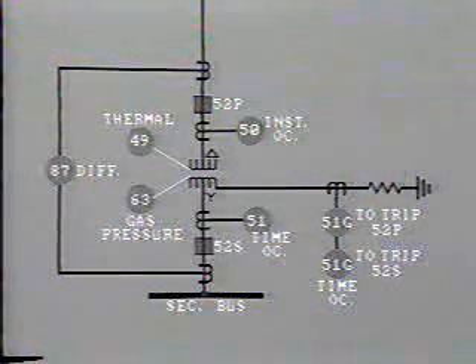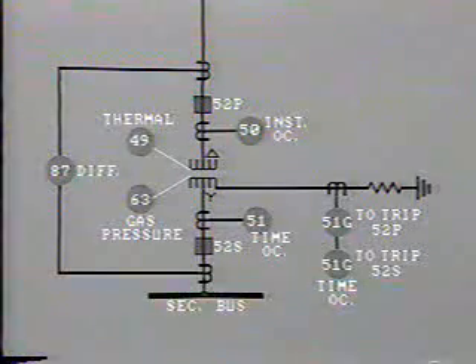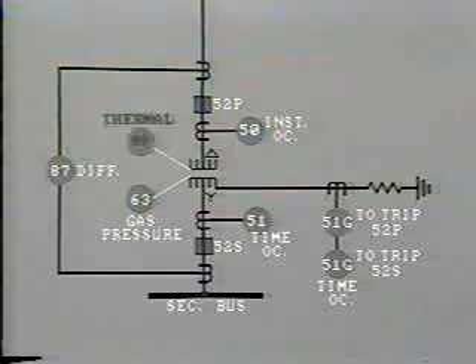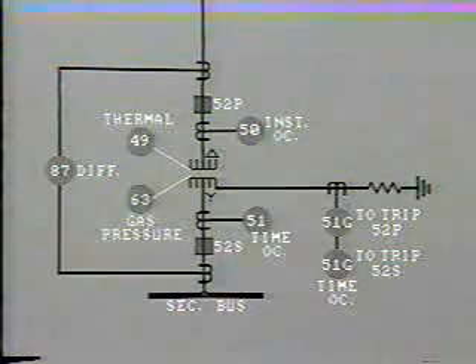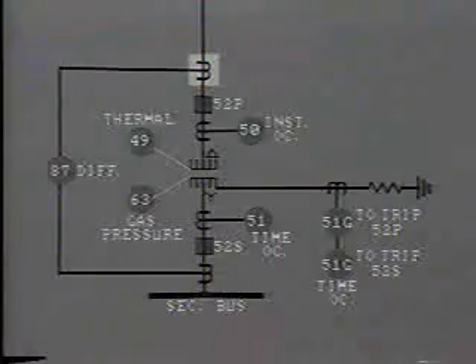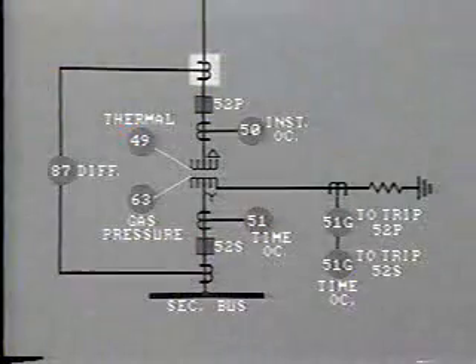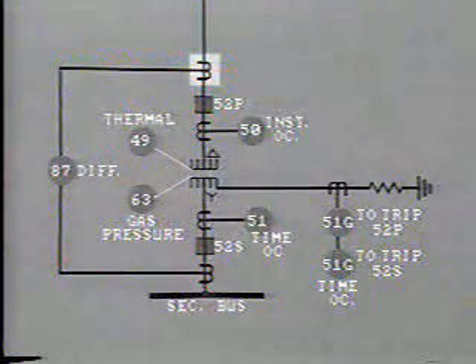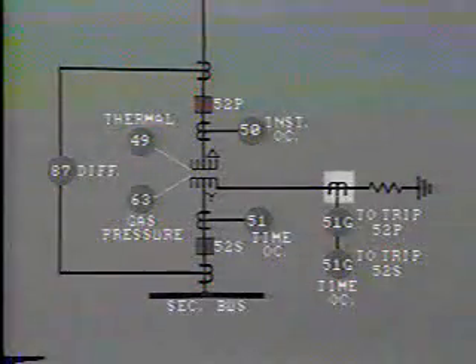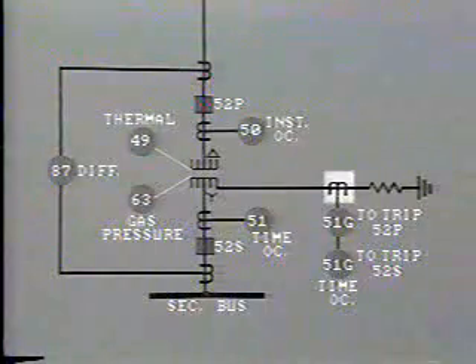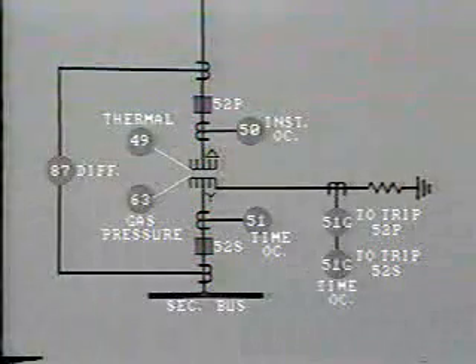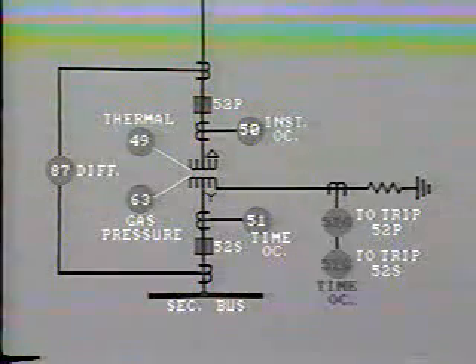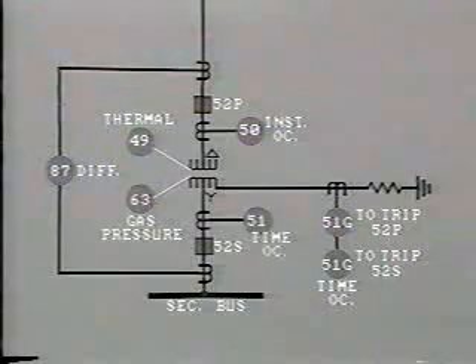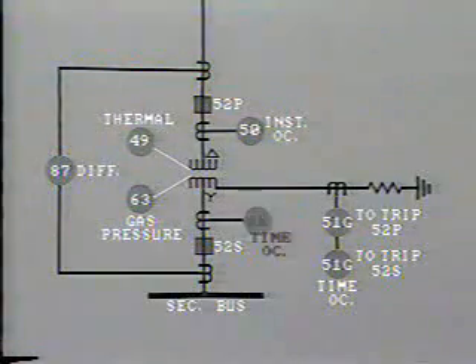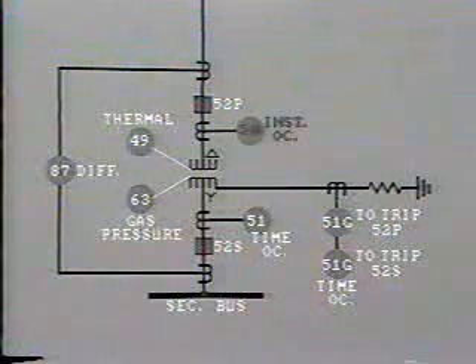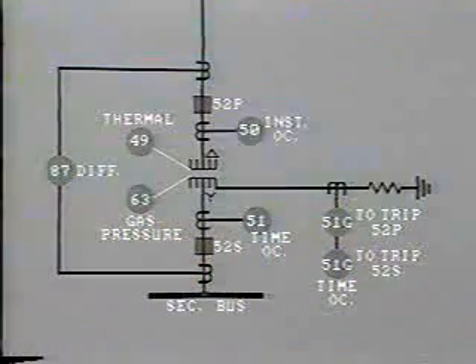What do these other device numbers represent? Looking up our reference list, we find that the transformer itself is equipped with a thermal relay, 49, and a gas pressure relay, 63. This is a commonly used symbol for a CT, but please make sure you are familiar with your own company standards. This CT is installed in the neutral to ground connection, measuring ground current. It feeds time overcurrent relays, 51G. Another time overcurrent relay, 51, is installed on the secondary output before the breaker. And what is this on the primary, device number 50? An instantaneous overcurrent relay.